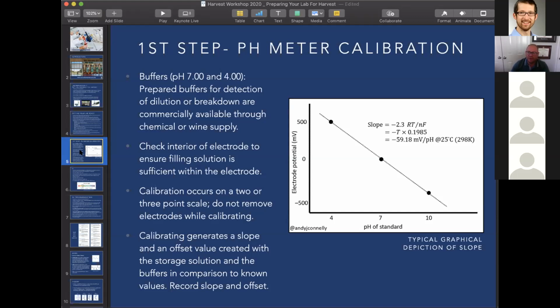And the slope is something that you hold internally. So for your winery, you would establish what your agreed upon slope is. Slope looks specifically at how accurate your reading is, in terms of the internal pH scale that the meter holds. So if you've got a percentage slope of like 80%, typically that would not be a value that we would accept in terms of an accurate pH reading.